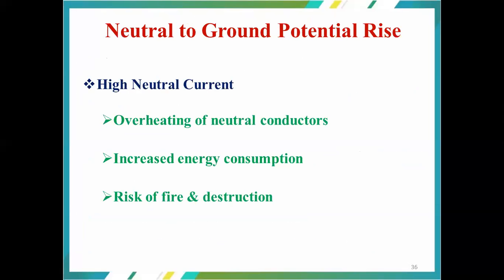Another ill effect is neutral to ground potential rise, and overheating of the neutral conductors, or increased energy consumption and risk of fire and destruction. This we can observe in large structures, large textile showrooms or petroleum refineries. We often have fire hazards or fire accidents because of this neutral to ground potential rise. As per the IEEE standards, it should be a maximum of 5 to 10 volts. If it exceeds, the temperature rise will be there, and firing also occurs.